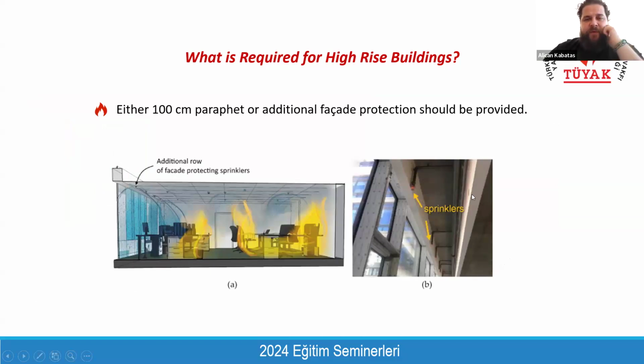And in Turkey, while you are designing your building, the facade design is also very related with fire and life safety. The main thing is the material selection during the facade design, and we already talked about within the architectural design lesson. Today we will see the details of the facade, which means as per Turkish fire codes, you either have 1 meter of parapet having a 2-hour fire rating between the floors, or you need to provide a closely located sprinkler facade protection to prevent fire coming out from the window and to reach to the upper levels. The main purpose is that.